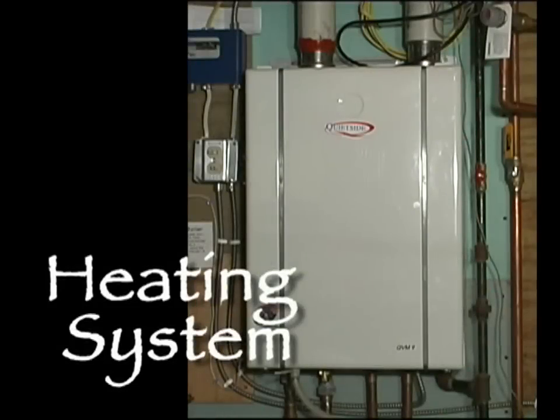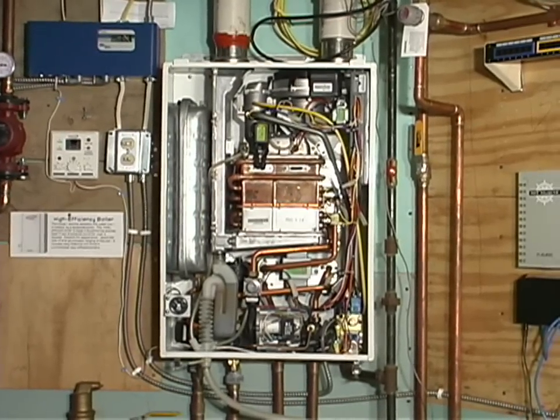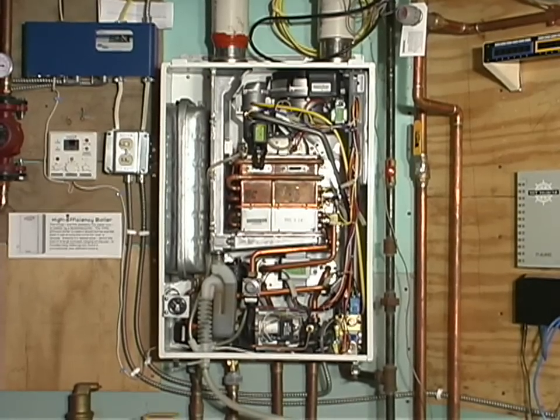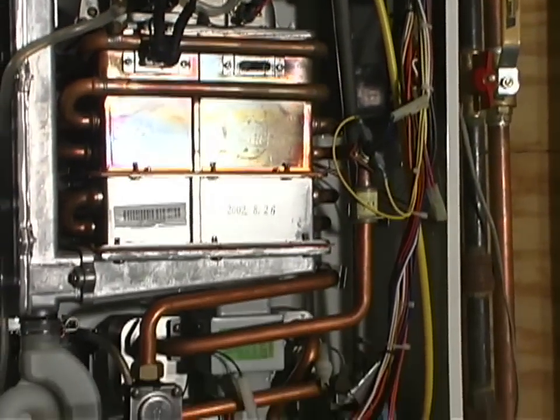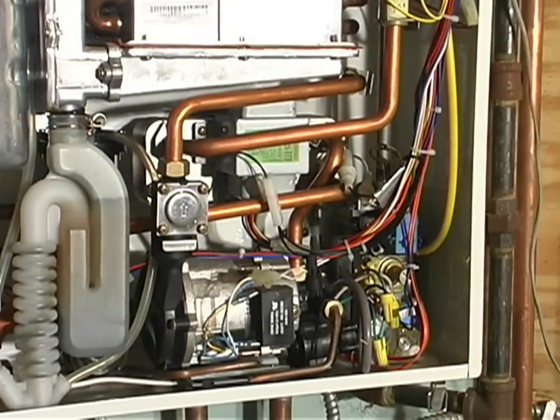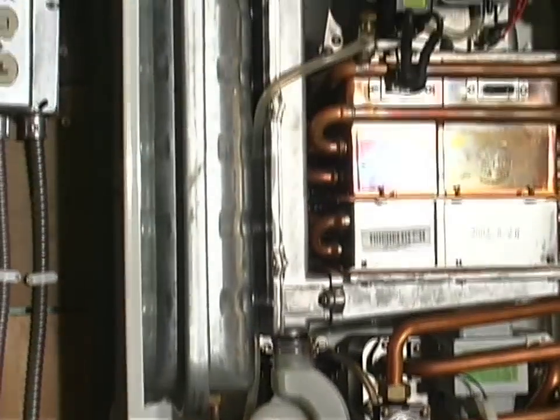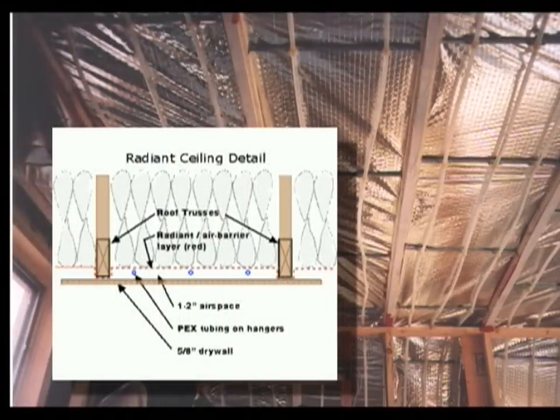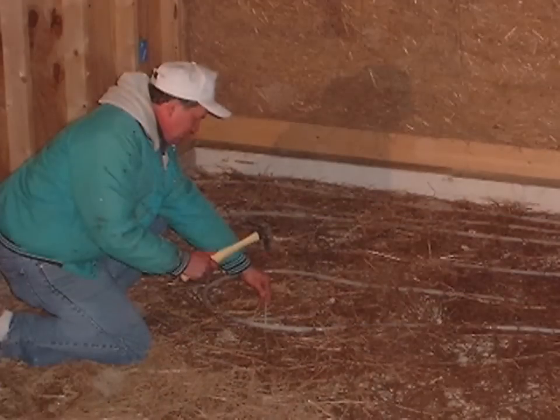This is the heat for the entire house plus the hot water, all in this little unit the size of a suitcase. This condensing boiler burns natural gas at 90% efficiency, similar to the most efficient furnaces and much better than conventional water heaters. The onboard computer gives priority to domestic hot water heating over space heating. This is one of the few heating units available that will operate efficiently at the very low heat loss rates typical of small, well-insulated homes. Heat is delivered to different zones via radiant ceiling tubes, refurbished cast-iron baseboards, and through tubes embedded in the slab floor.